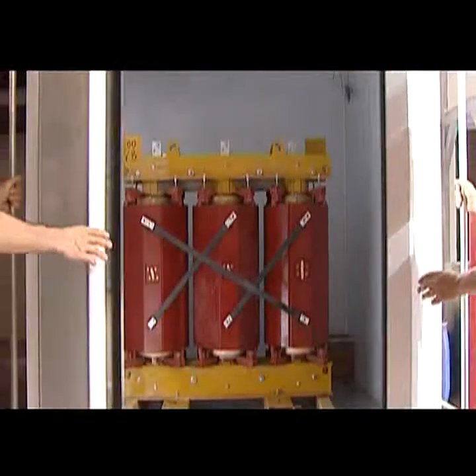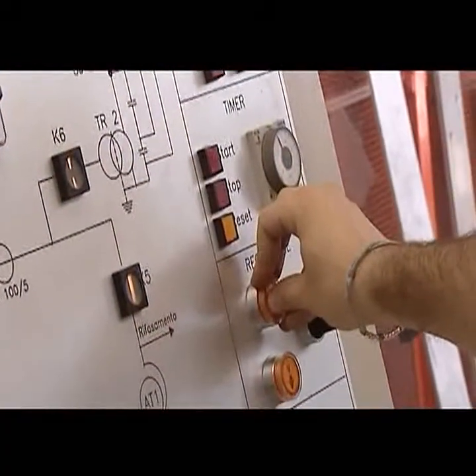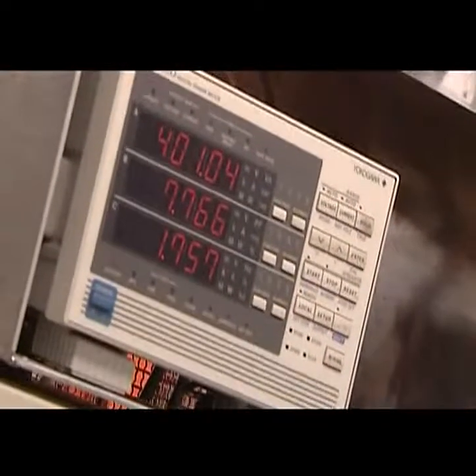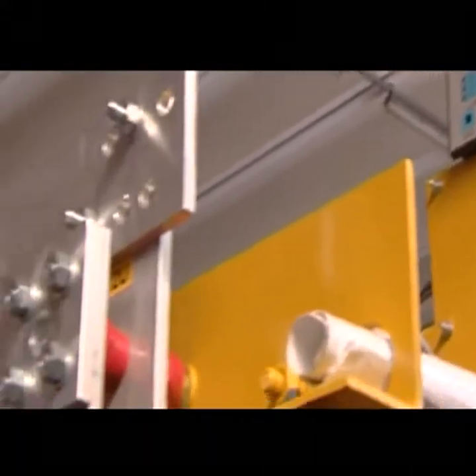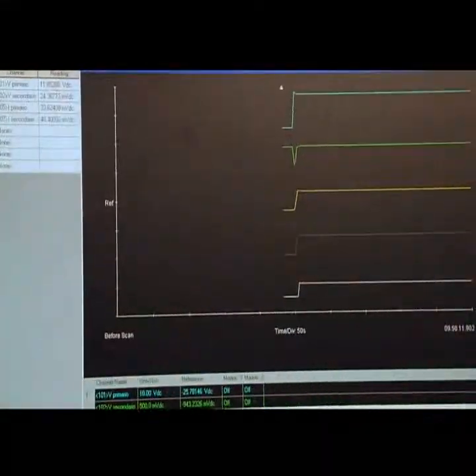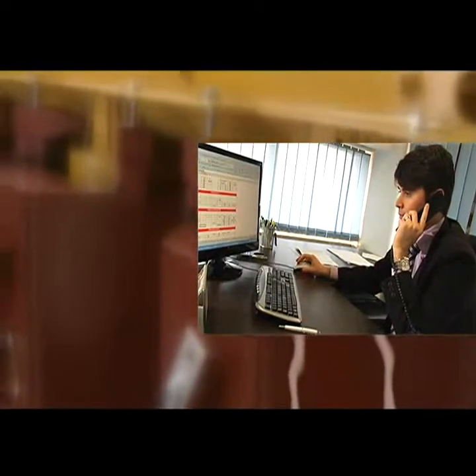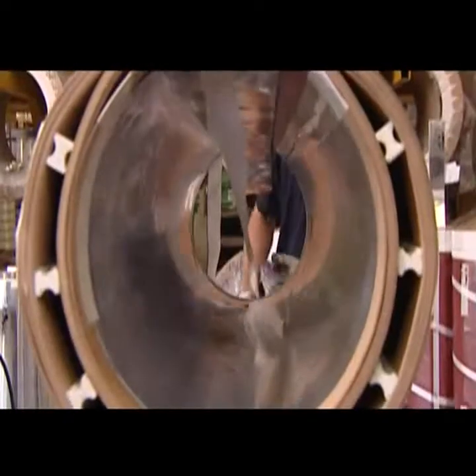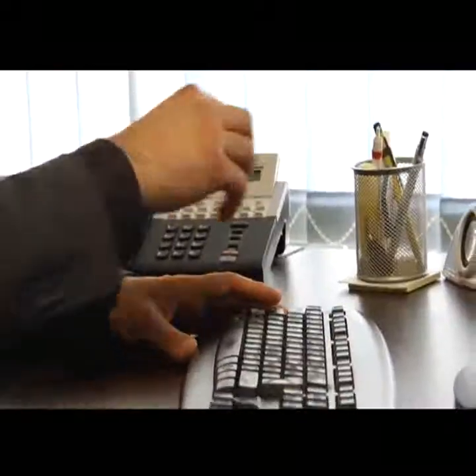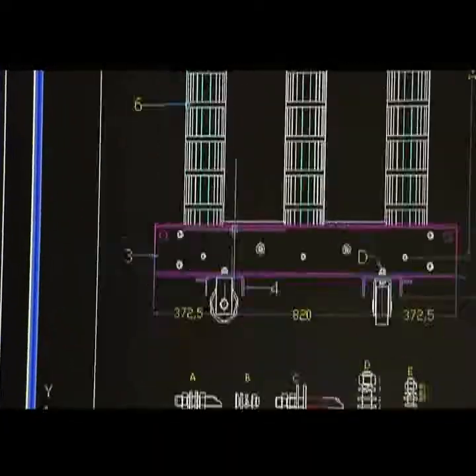Moreover, ALTRAFO can stress thermally the transformers going from -25 degrees Celsius to 140 degrees Celsius, verifying later their mechanical and electrical parameters. Or it can put them in tropical environment with very high humidity in order to check their dielectric tightness. ALTRAFO performs time after time heating tests, studying conditions, ensuring the right losses disposal of transformers. In addition to technical features of the transformer, the external conditions of ventilation and cooling too have the common aim to control working over temperatures of windings and core. ALTRAFO pays particular attention to product research and development. In fact, in a more and more competitive market, it is not possible to maintain high-quality standards of the product without a continuous planned revision.